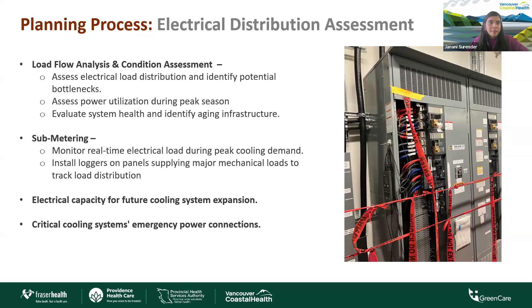So after completing all the initial assessments, we identified a list of cooling strategies that fit into all of these buckets here. And of course, the primary focus was on the cooling capacity. So many of our systems lack the capacity to meet the future demand. Through our cooling load calculations, we were able to pinpoint the capacity shortfall and identified the chiller and the cooling tower upgrades for the coming years.